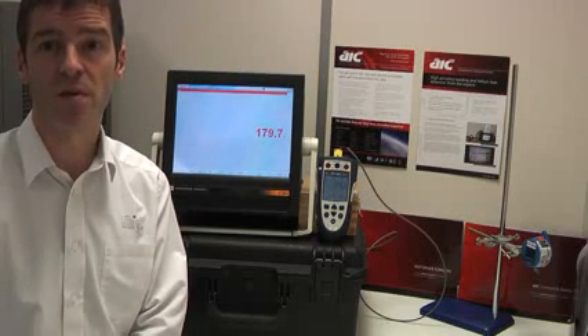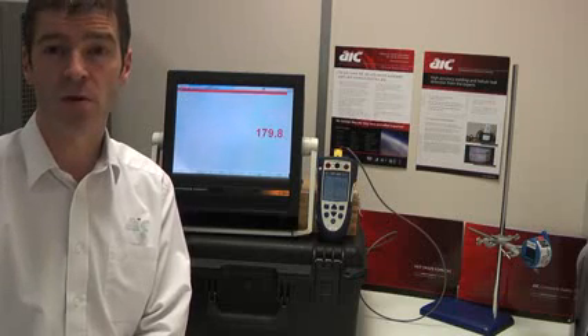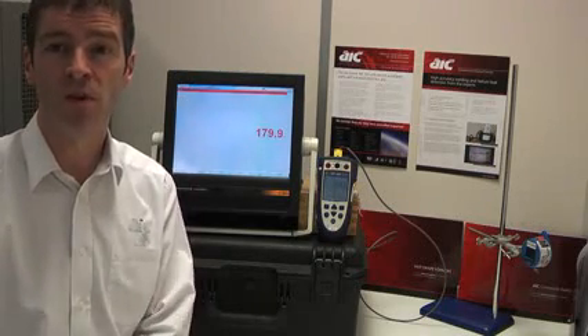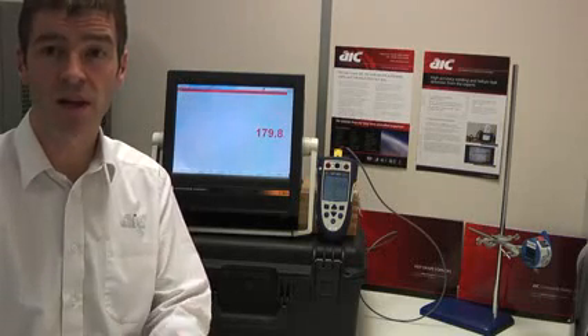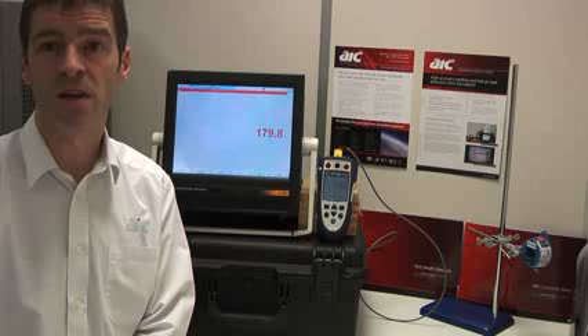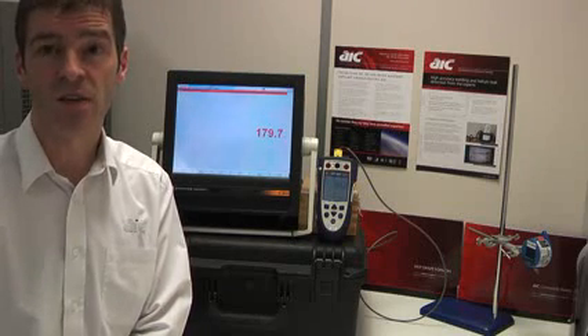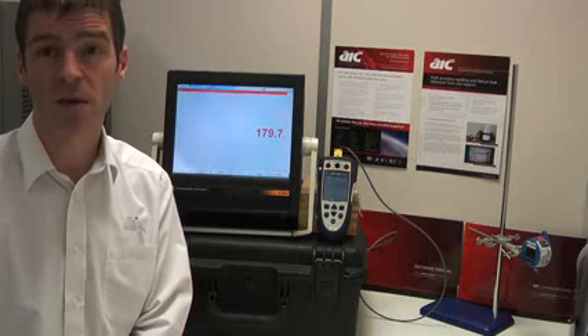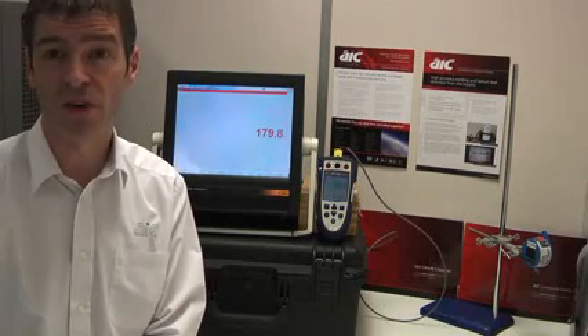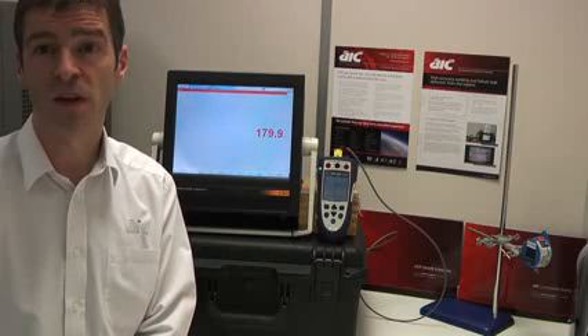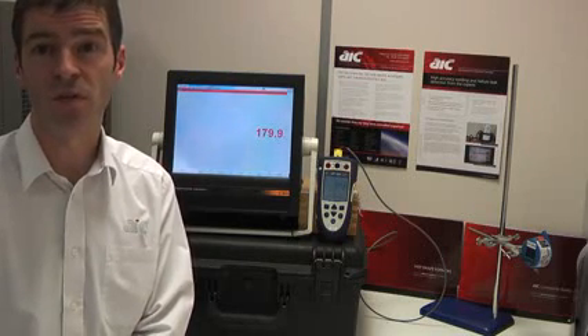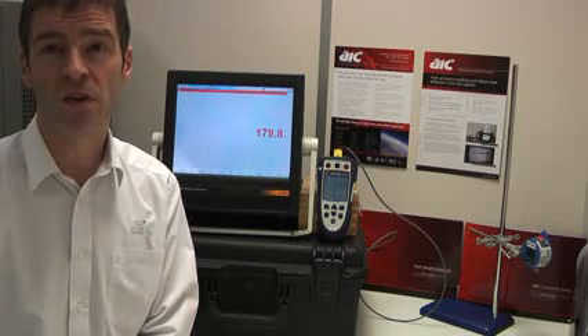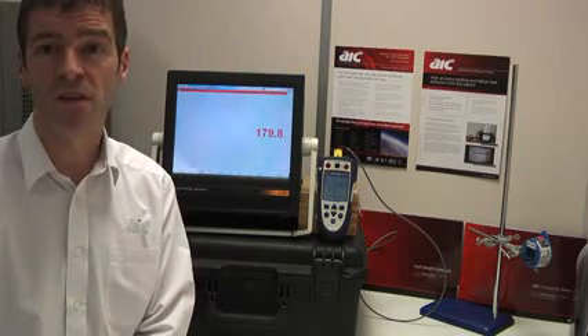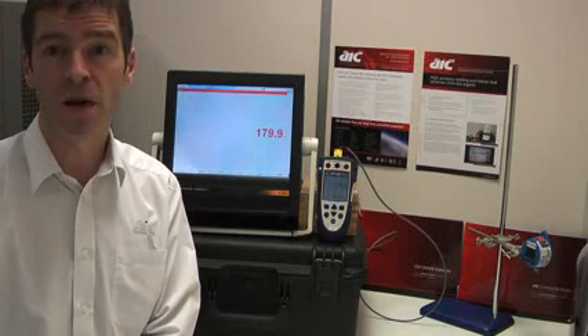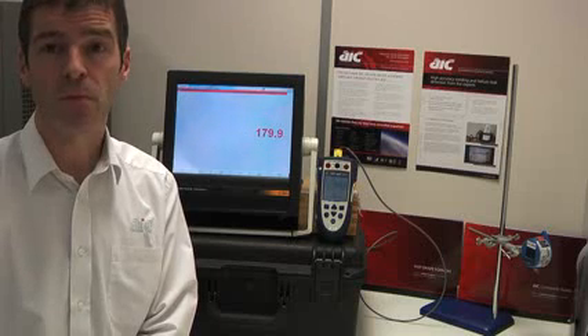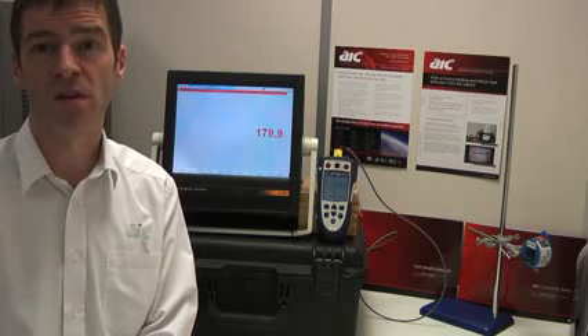The alternative method, which is recommended, is to carry out an in situ calibration where you actually take the machine up to its operating condition with a reference standard next to it, completely independent, and compare the readings using that method. Failing that, the only alternative is to replace the cable. On some machines that may be the most cost-effective way of doing it, but for many autoclaves and ovens with dozens and dozens of thermocouple cables installed, the cost will be prohibitive. But an in situ calibration, provided you know that all of the batches of thermocouples are the same and they've seen the same cycling, ought to provide good assurance that your measurements are indeed accurate.